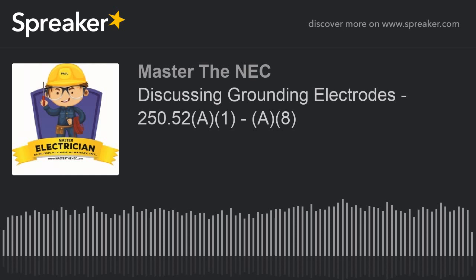Concrete encased electrode, that's (A)(3). (A)(4) is a ground ring. (A)(5) is rod and pipe electrodes. (A)(6) is other listed electrodes. There are going to be some chemical type things that are other listed ones. (A)(7) is a plate electrode. So that's your (A)(1) through (A)(7). And then you have (A)(8), which is called local metal underground systems or structures.